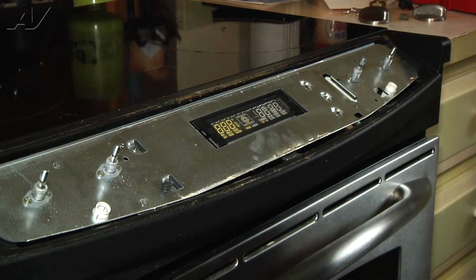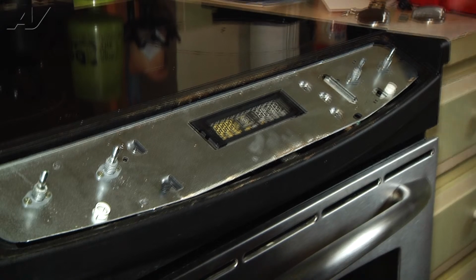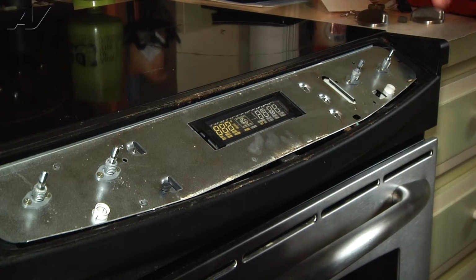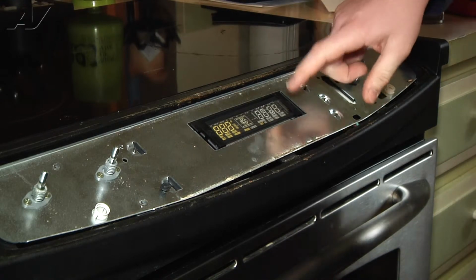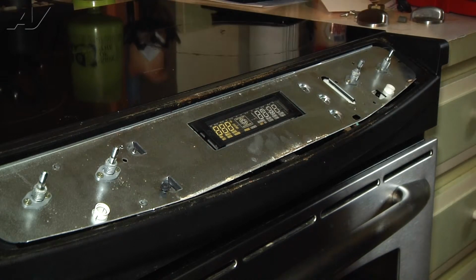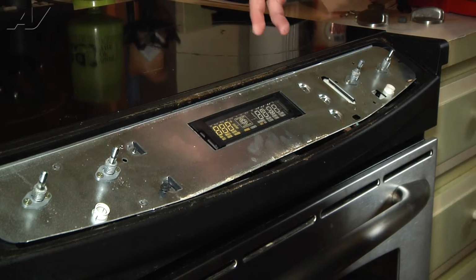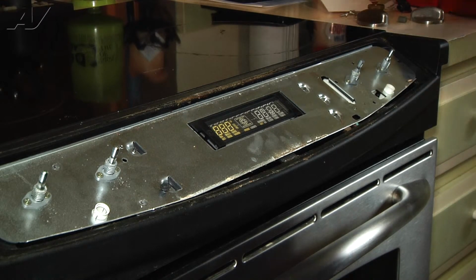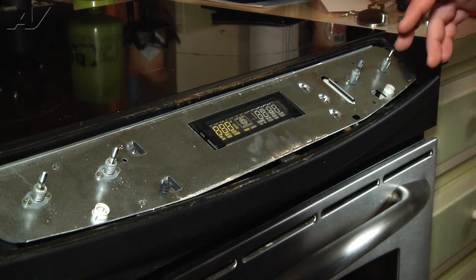One thing with this error code: with an F7 error code, like we were saying, it can either be the control board or the keypad. In our case, we know it's the keypad automatically because some of the buttons were not working.